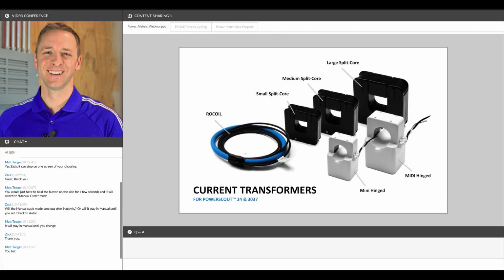There are 3 different styles of CTs. There's the mini and MIDI. These are the smallest ones that would handle the lowest level of current. The medium style, the medium split core, has 3 sizes: small, medium, large, and that's the next step up in the amount of load that these can handle. Then there's also the rope style Rogowski coil CTs that can handle up to 4,000 or 5,000 amps, depending on which of the meters that they're communicating to.